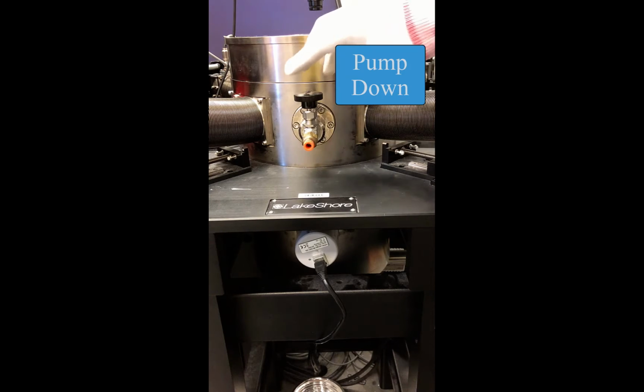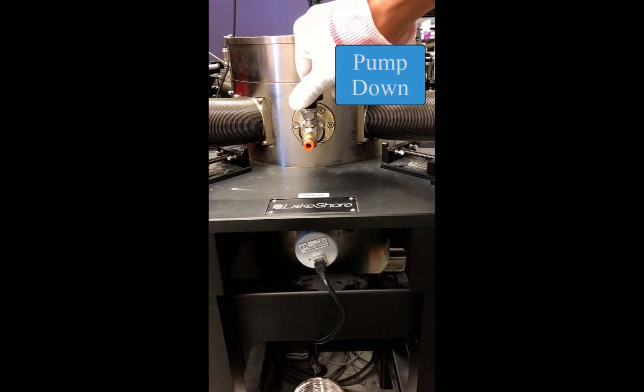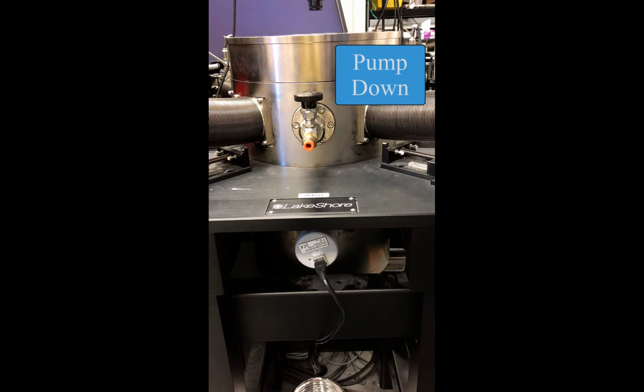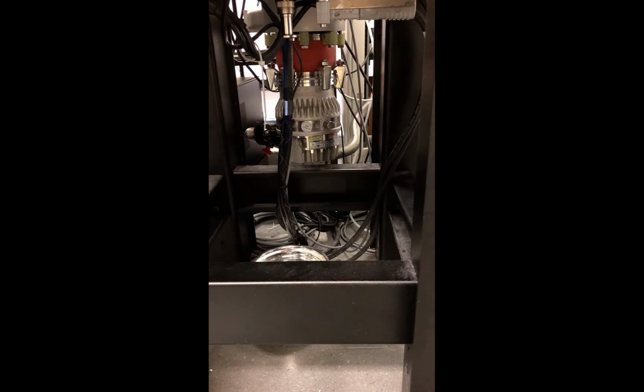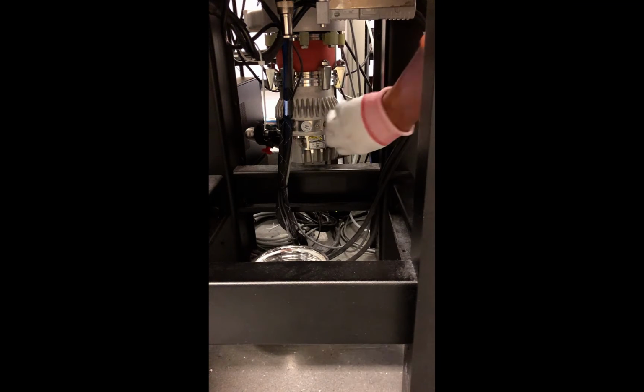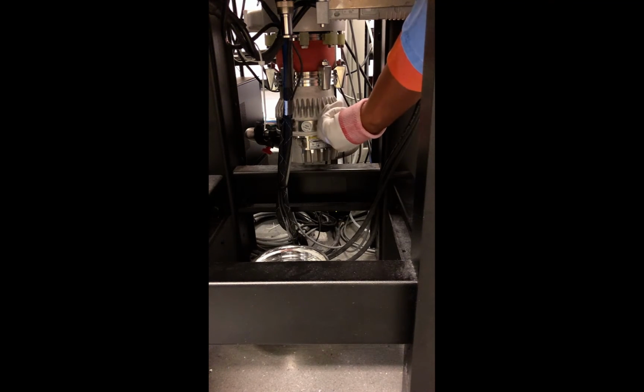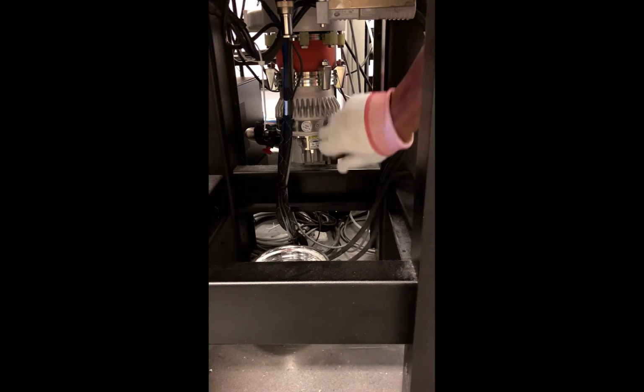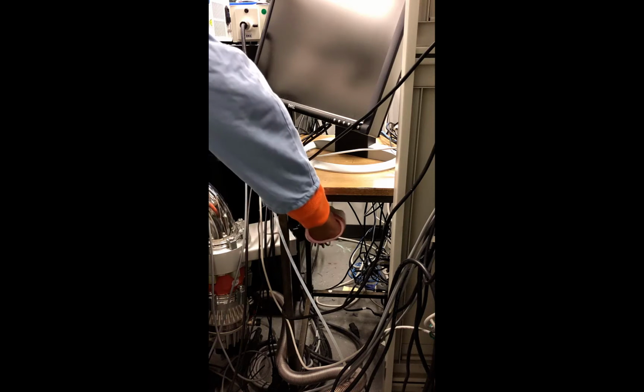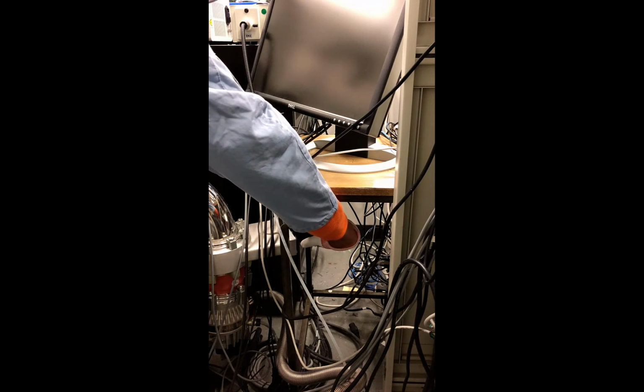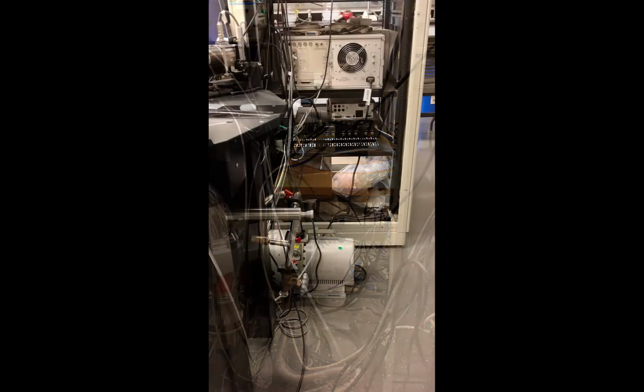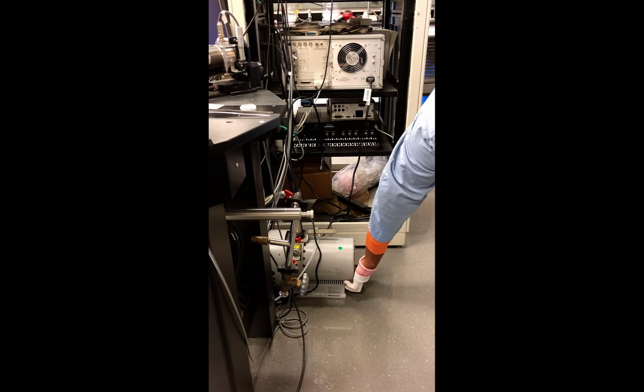To begin the pump down procedure, first close the sample chamber purge valve. Now close the turbo pump vent valve. And then pull open the vacuum isolation valve. Finally, turn on the roughing pump.